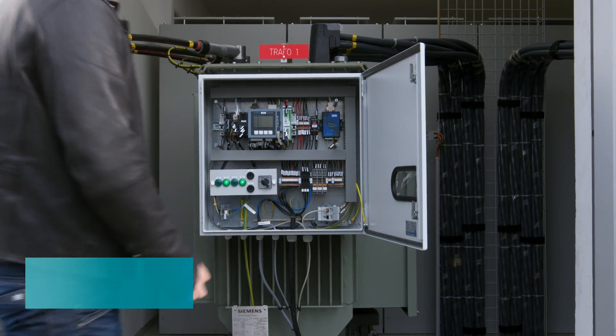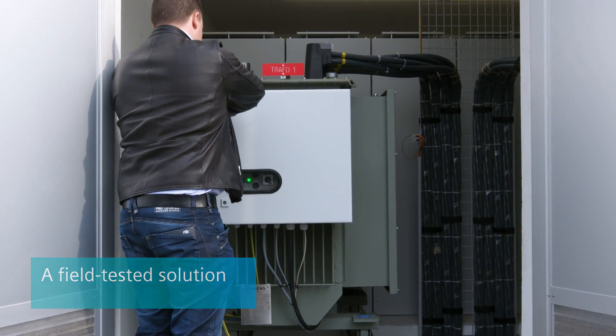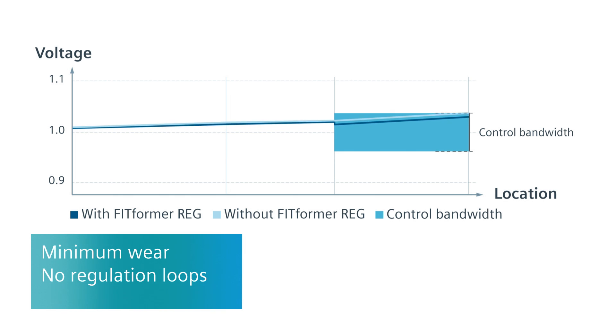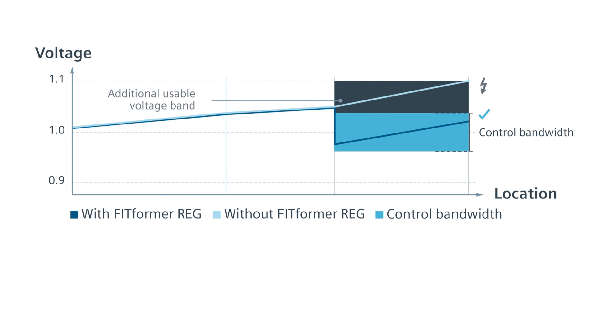With its three-stage control on the low-voltage side, FITformer REG has proven itself in field tests with many years of operation under real-world conditions. Voltage remains in the specified range in all situations. Wear is kept to a minimum, and wide voltage control ranges prevent regulation loops with the medium voltage level.